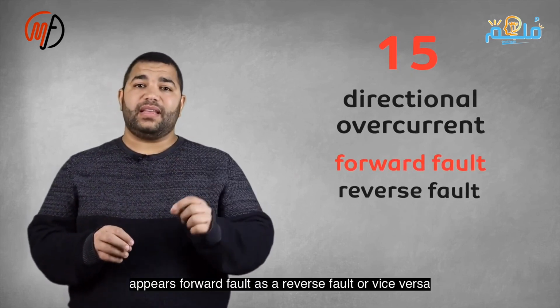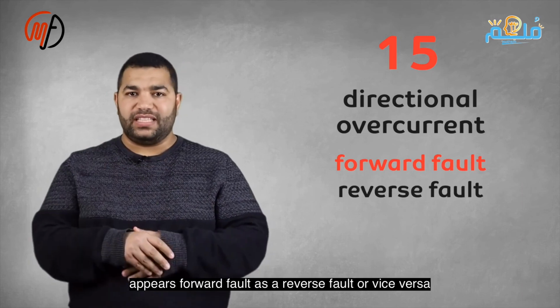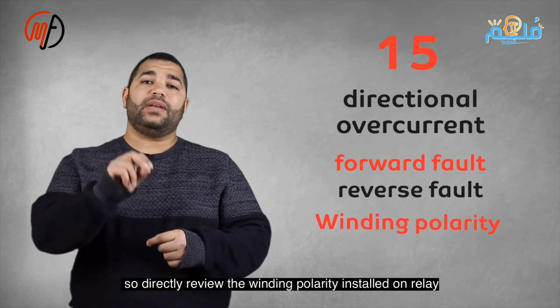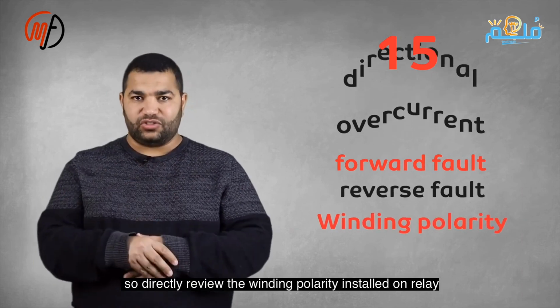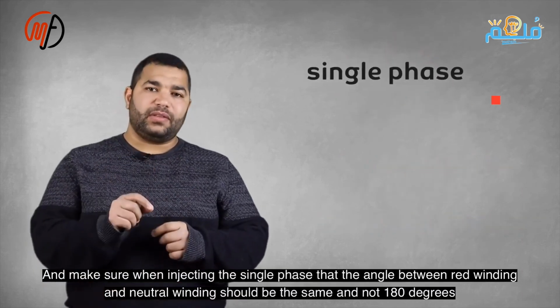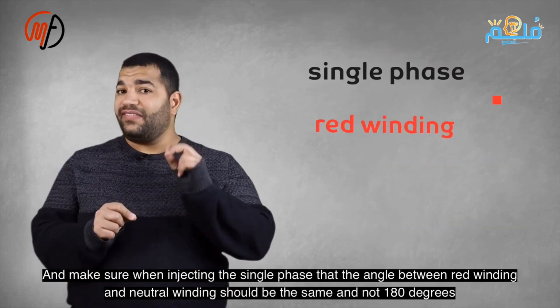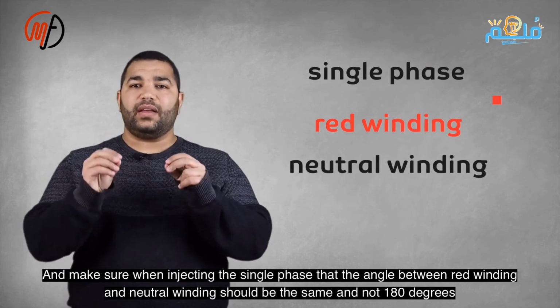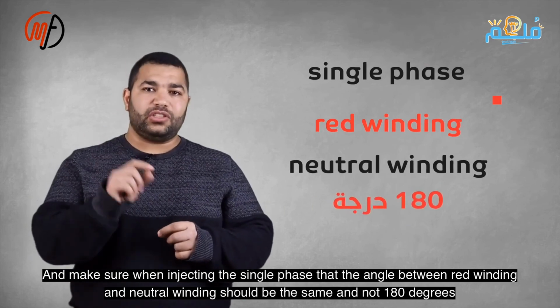Verify winding polarity connected to the relay, ensuring red and neutral winding angles match, not 180 degrees during single-phase injection. Confirm if the relay characteristic angle is lagging or leading. Manuals may vary in describing this angle, so review them to understand the relay's perspective. Ensure you're adjusting the current angle, not the voltage angle, following directional protection principles.